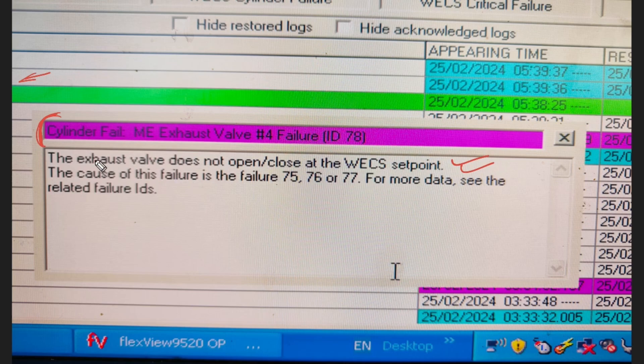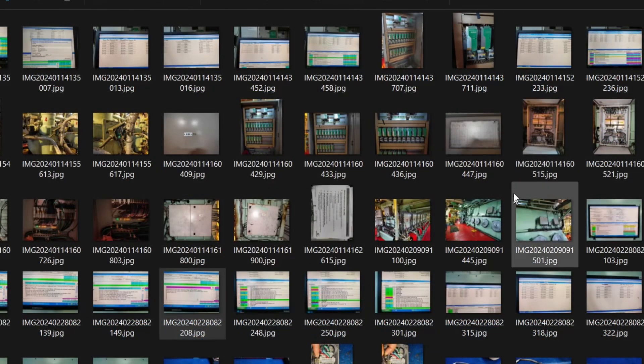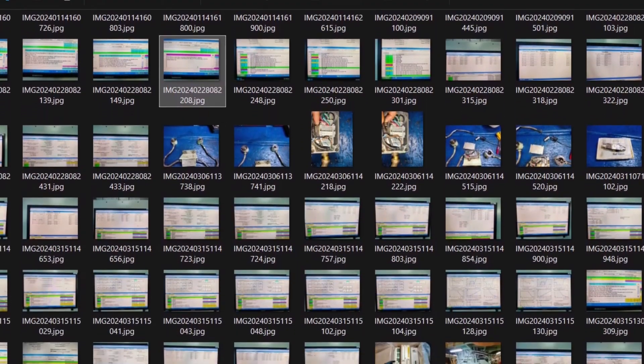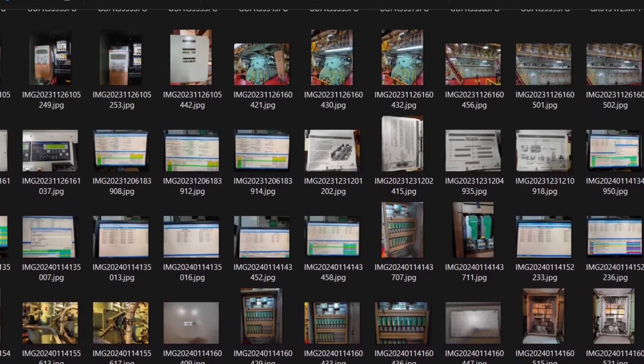The troubleshoot guide helps you 99% of the time solve your problems. It will say things like 'cylinder fault' or 'exhaust valve does not open and close' along with the WECS set point to check. Always double-click on the alarm and check what messages pop up - 99% of the time you are going to rectify the problem using the troubleshoot guide available in FlexView.